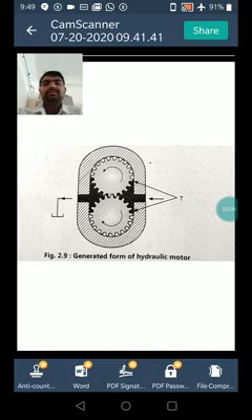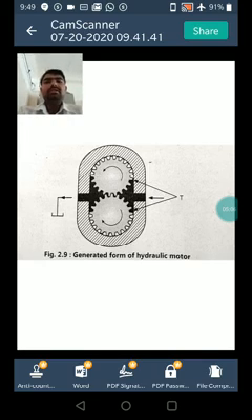Okay, then now we see the working. The torque developed is a function of the force exerted by the oil pressure on one tooth. The fluctuation of torque generated can be smoothed out by using a large number of teeth. The volumetric displacement, however, decreases with the increase in the number of teeth, with low output pressure or low output power for the given size.